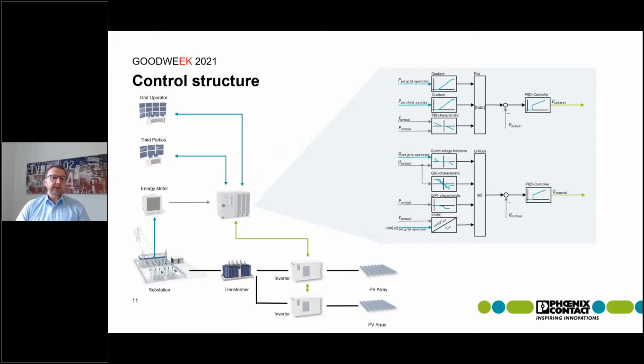At the end, the actual energy is measured at the substation by an energy meter or a power analyzer, whatever. You get the actual information at the grid connection point. Therefore, you calculate the new set points and send the data to the different inverters. The inverters handle the power as active power or reactive power. There's also bidirectional communication between your inverters and your power control unit, because the values of the inverters are also read by the power control unit.